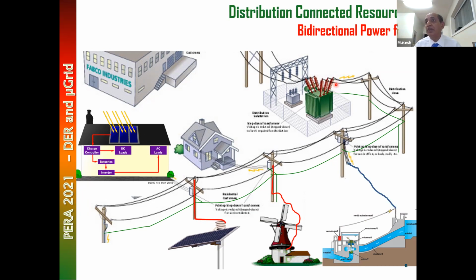So we need to find, basically, distributed generation can only practically be connected to a low voltage grid, that is a distribution system, or maybe a sub-transmission system, not to a 500 kV extra high voltage transmission system. That's where our traditional centralized generation was connected. And again, when we are connecting them, what kind of issues are we going to introduce? So first, for the economics of distributed generation, we can only connect to the low voltage grid.